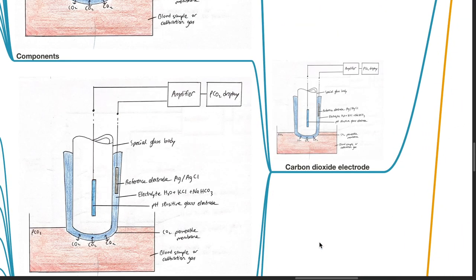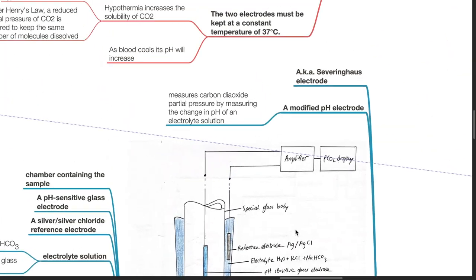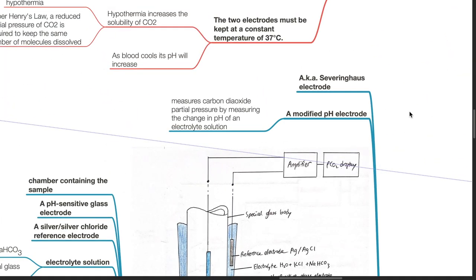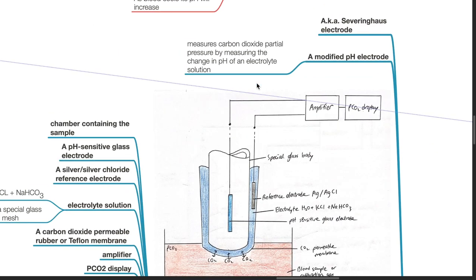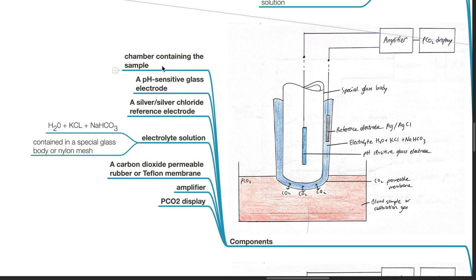The carbon dioxide electrode, also known as the Severinghaus electrode, is a modified pH electrode that measures carbon dioxide partial pressure by measuring the change in pH of an electrolyte solution. Components include a chamber containing the sample, a pH-sensitive glass electrode, a silver-silver chloride reference electrode, an electrolyte solution consisting of H2O plus KCl plus NaHCO3 contained in a special glass body or nylon mesh, a carbon dioxide permeable rubber or Teflon membrane, an amplifier, and a PCO2 display.